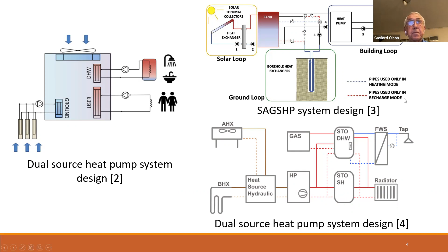Yeah, let's go along to the next. So here we have some direct quotes on the bottom from, in the first case, reference number 1, from the people in Belgium that did not have an air source mode. They could not feed the dry cooler output into the heat pump. They had only preconditioning of 2 different bore fields. But believe it or not, the summation of the borehole length in both of those bore fields was 47% of what would be needed for a single bore field that was not multi-source. So this is something which I find pretty interesting, but if you have any doubts about it, I'd recommend you go back and read that document, reference number 1.